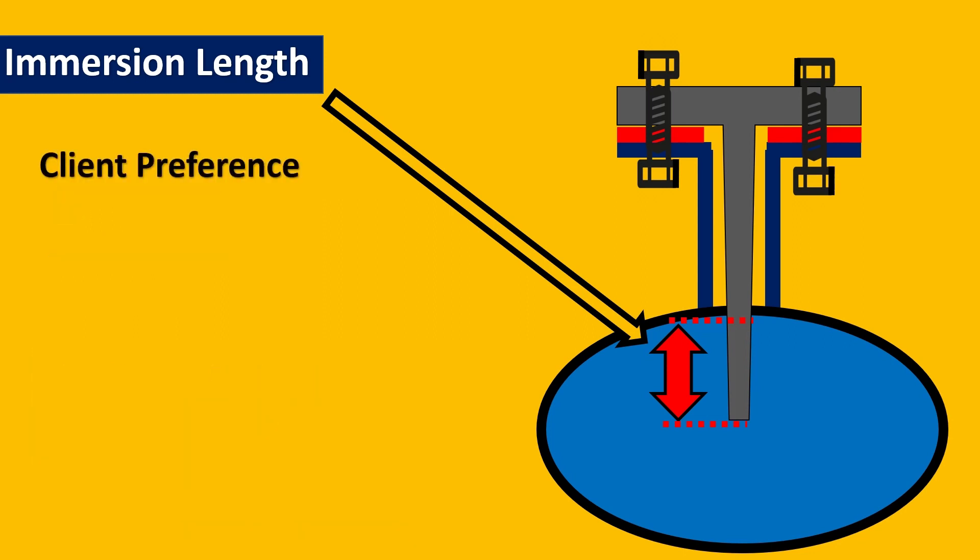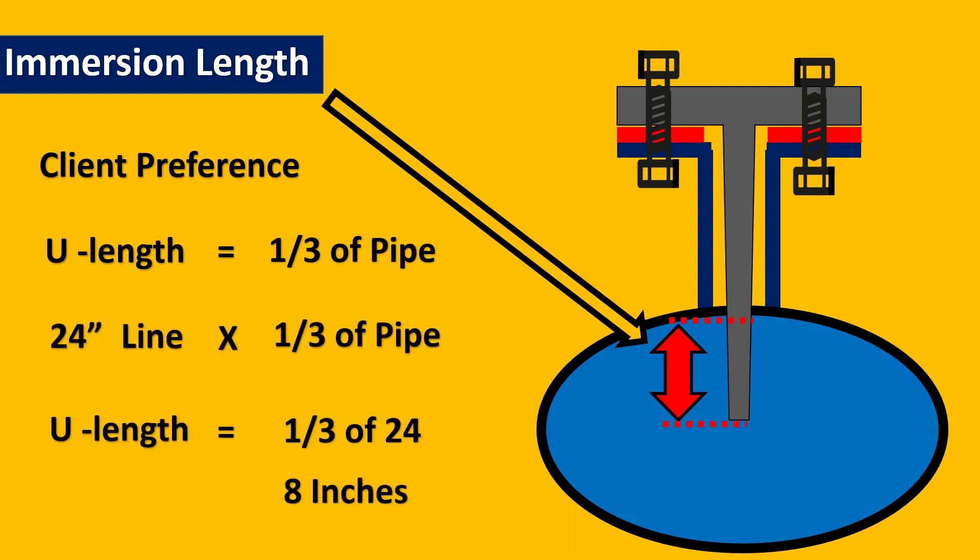Finally, certain clients have their own preferences. For example, the U-length they say should be 1/3 of the pipe. So if you have a 24 inch line times 1/3 of pipe, it is going to be 8 inches. So basically the client wants that it should go around till 8 inches. So you have to depend upon what criteria you use for immersion.